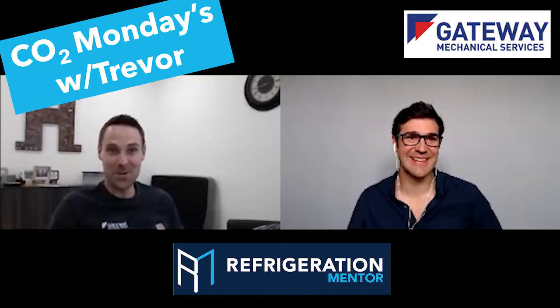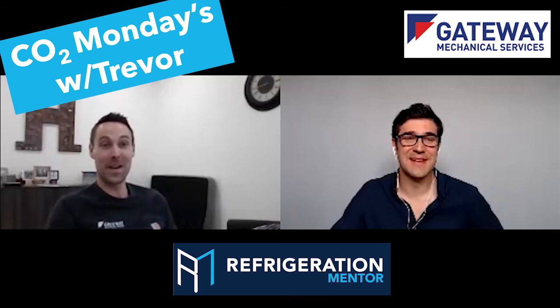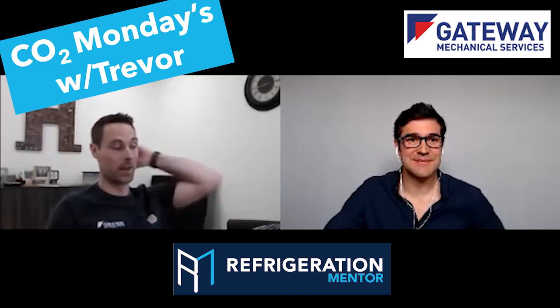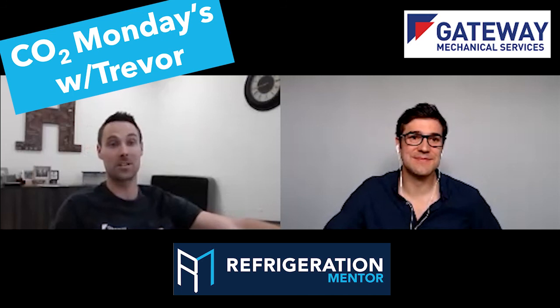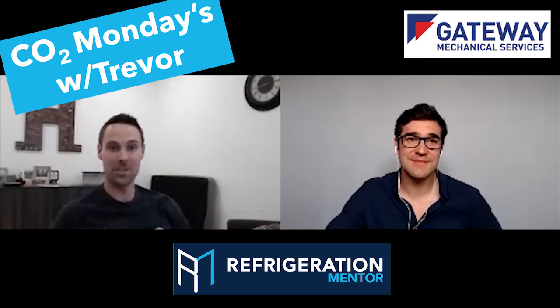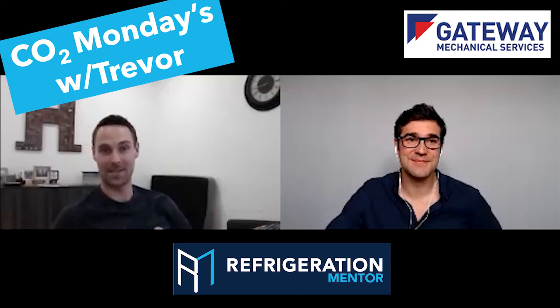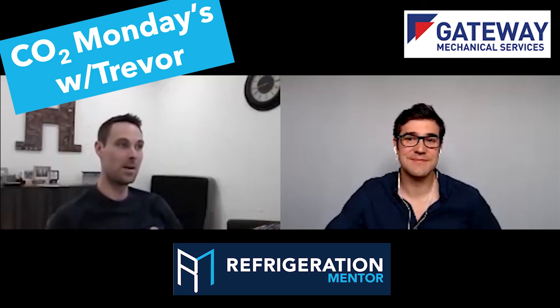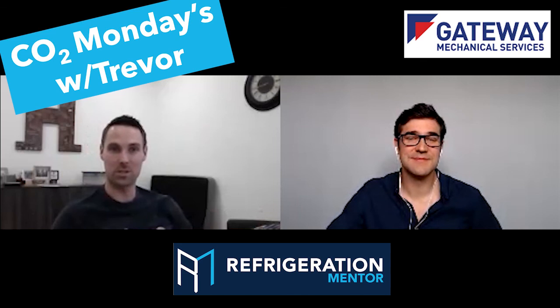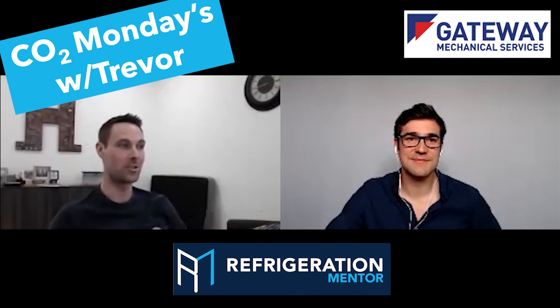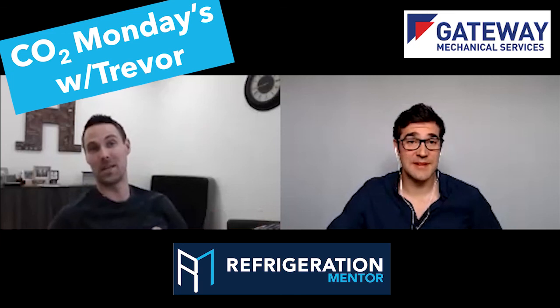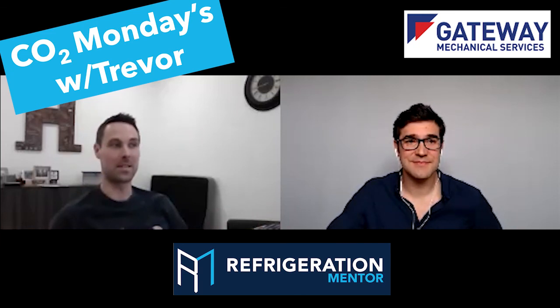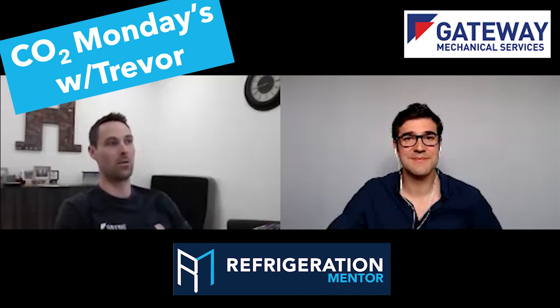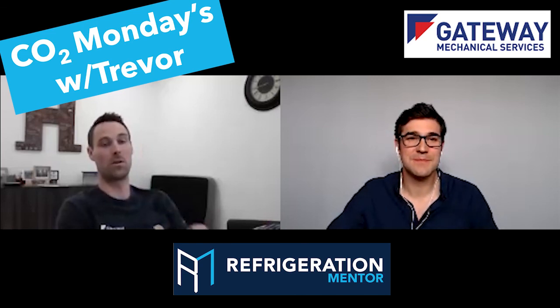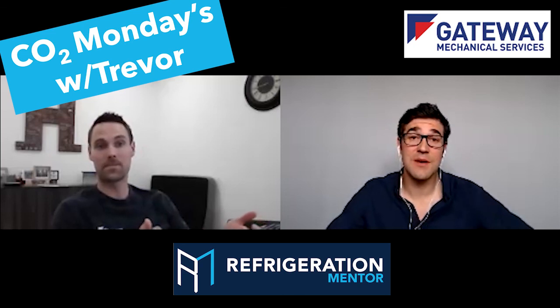That's huge. Yeah. So once I got my head fully wrapped around that, I actually had to reach out to Sporlan, because they don't even have all this information out there yet. They have it internally. I was able to find low temperature charts pretty easily, but for medium temp application they actually had to send that to me. I was looking at some of the valves I had, and one of the most common service calls we have at our CO2 stores is EEV valve failure. Oh wow.